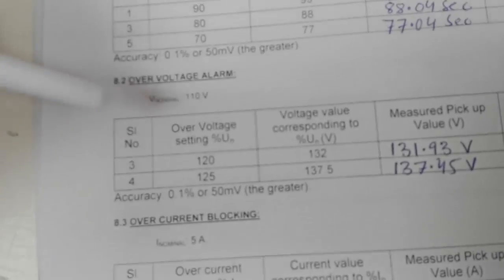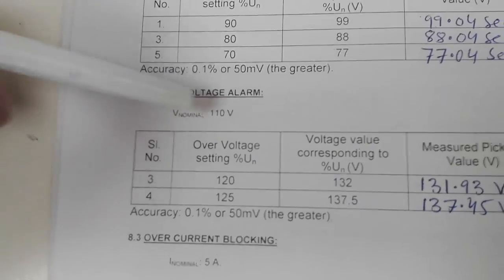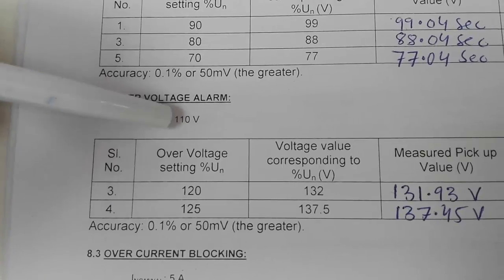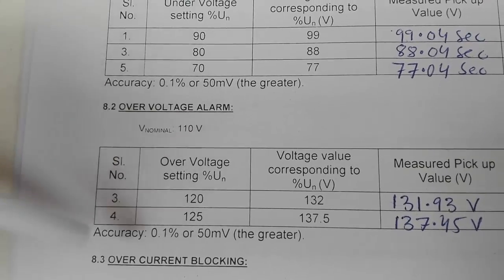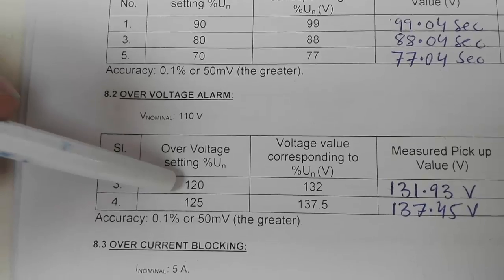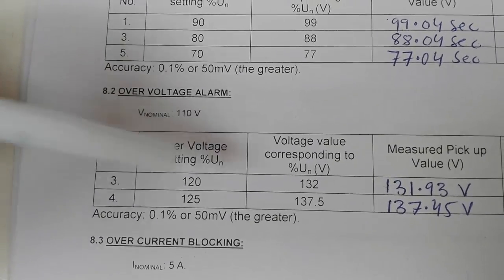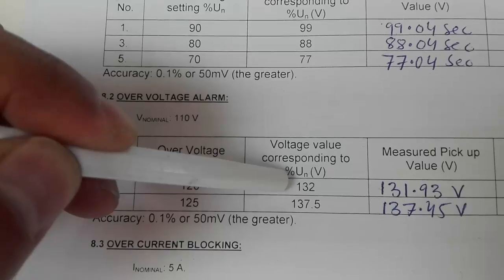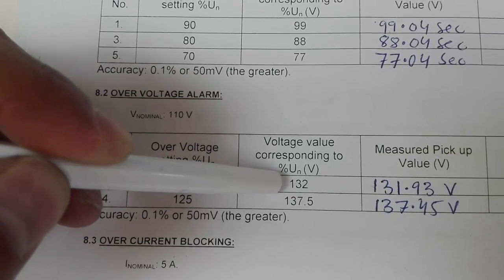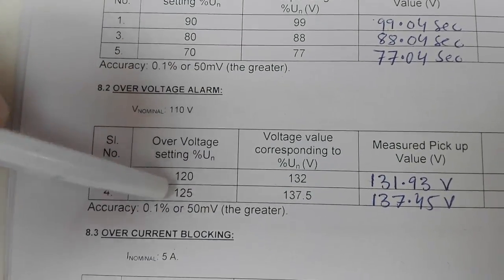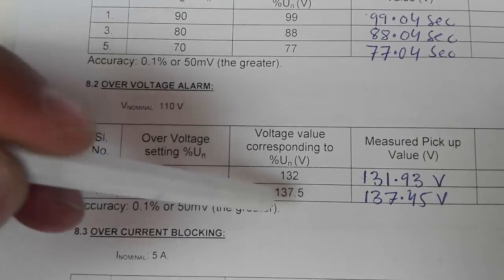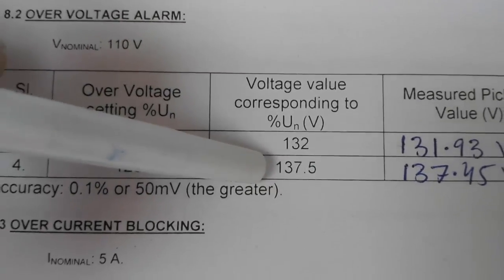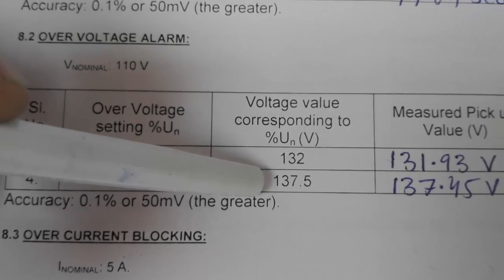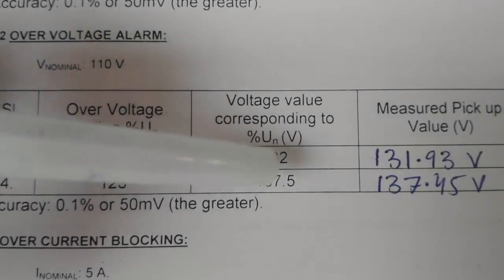Now here we will test for over voltage alarm. Nominal voltage same 110 volts. Now first we will do 120% of 110 volts, that becomes the value 132. For this we will check the alarm, and then simply for 125%, that is the voltage we will inject through Freja, 137.5 volts, and then we will check the values. Now first inject 132 volt, please.